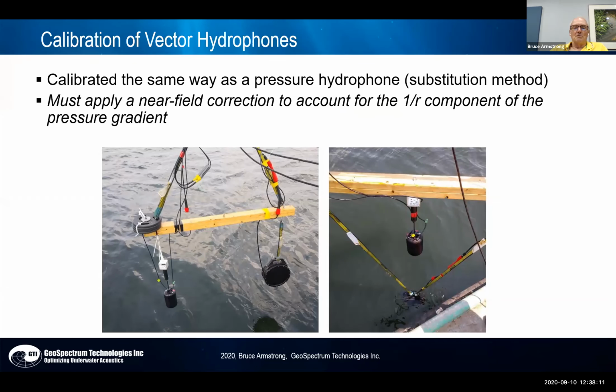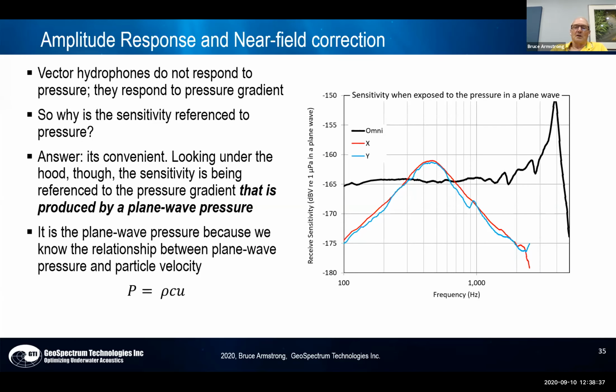These are the lengths you have to go to in order to calibrate these things in water. You calibrate them in the same way as your pressure hydrophone, except that there's a complication. You must apply a near field correction. That's because these are responding to pressure gradient, and when you're near a sound source, there's an extra component of pressure gradient that doesn't matter to a pressure hydrophone. And this is what a calibration curve looks like. The omni, labeled omni there, that's your pressure hydrophone. It has a flat response. The vector hydrophone, the XY channels, have a response that rises at 6 dB per octave, reaches a peak, and then falls at 6 dB per octave.